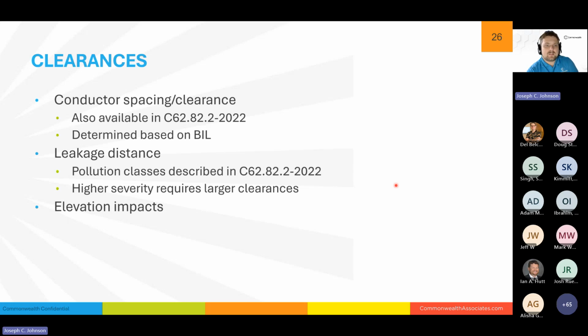The next is leakage distance. So there are pollution classes that are described also in the same standard, and these go from very light to very heavy. And this is something like having an arrestor and a substation on the coast. You get a lot of salt spray that will actually coat your insulators, and your insulators can degrade and not have as good of insulating properties. Same thing if you're next to a factory or maybe a lot of homes and there's lots of potential pollution in the air. There's, like I said, very light to very heavy. Depending on that class, there's a larger separation distance needed, and the leakage distance is usually found in the data sheets of the arrestors.